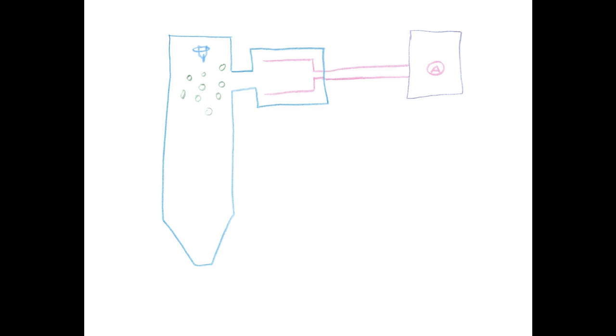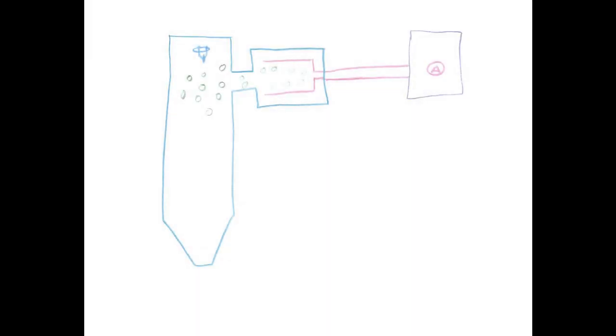Ion pumps are commonly used in systems like electron or ion columns to achieve high vacuum, which is pressures down to 10 to the minus 7 to 10 to the minus 10 millibar range. Inside the vacuum chamber or the column, stray molecules drift around. Some of them wander into the ion pump, which has electrodes charged up to a very high voltage, around 5,000 volts. That voltage is so high that it actually ionizes the gas, giving the atoms a charge. Once charged, they're accelerated to the metal plates and they get embedded there permanently. So the pump gradually removes gas from the system. That's why it's called an ion getter pump.